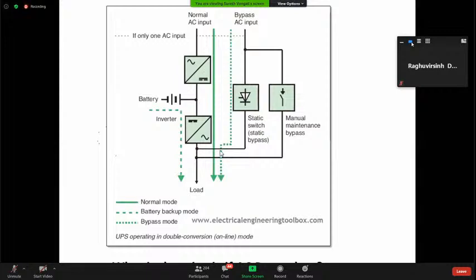When you see the equipment in theory versus real time equipment, I've seen we have switches separately. If you want to move to maintenance bypass, or move back to manual, there is a three-way switch installed. You can keep it in normal, in bypass, or in manual bypass, so the operator has the opportunity to move in any direction.